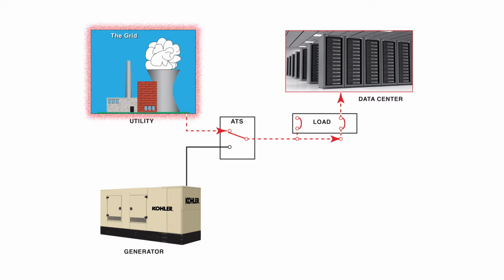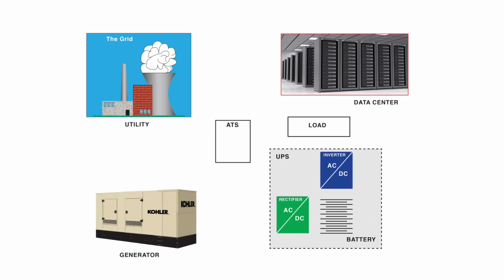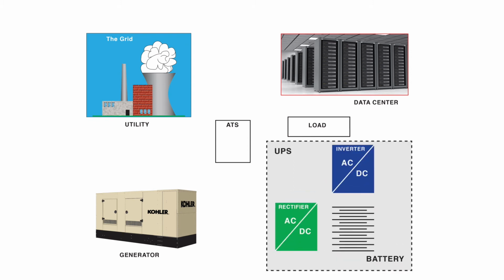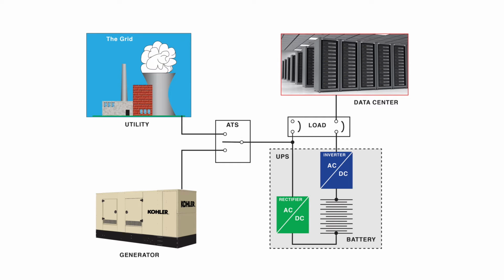to standby mode. However, data center providers have zero tolerance for power interruption, even for a nanosecond, so they feed power to the data banks through an uninterrupted power supply, or UPS, system. During a power outage, the UPS system supplies uninterrupted power to the load while the standby system runs up to speed. Power is usually supplied from the utility.